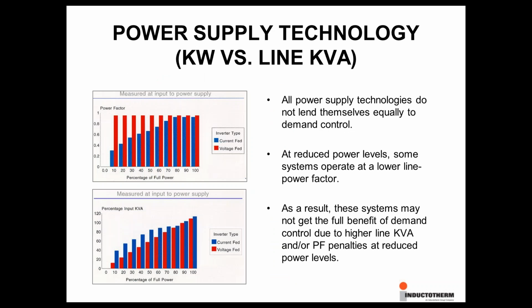Another part of performance associated with power supply technology is kilowatt output versus line kVA and line power factor. All power supply technologies do not lend themselves equally to demand control. As shown in these charts, one technology maintains a consistent high power factor at all power levels, whereas some technologies operate at a lower line power factor at reduced power levels. This also means that at reduced power levels, your input kVA will be higher as compared to those running at a consistent high power factor. As a result, these systems may not get the full benefit of demand control due to the high line kVA or power factor penalties at reduced power levels.